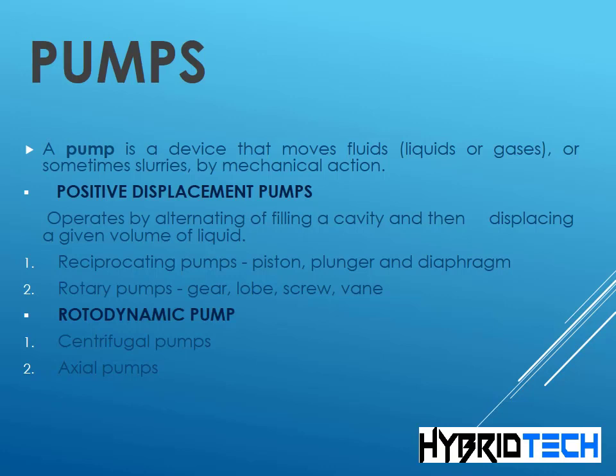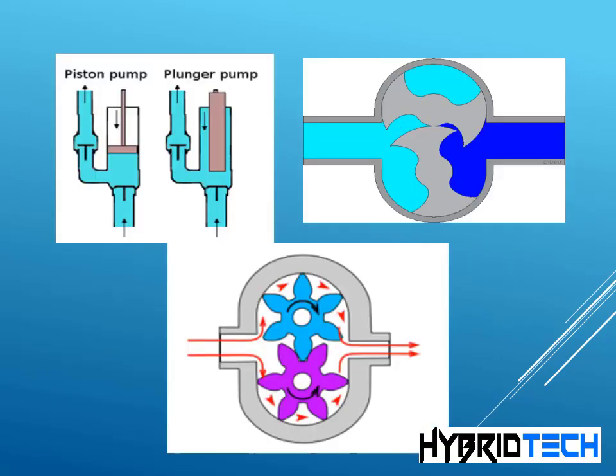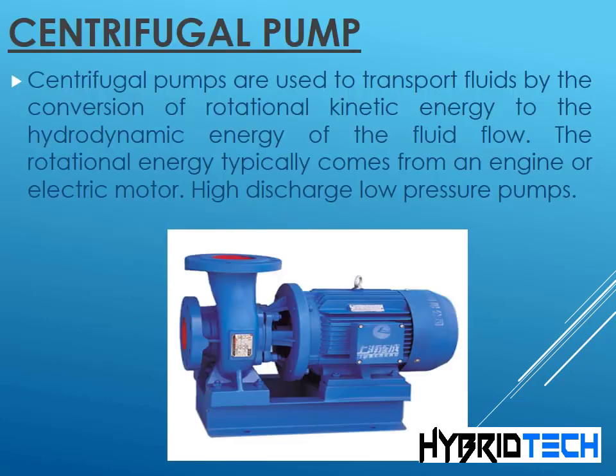Types of pumps include reciprocating pumps (piston, plunger, and diaphragm), rotary pumps (gear, lobe, screw, vane, rotor), and dynamic pumps such as centrifugal pumps. Centrifugal pumps are used to transport fluids by the conversion of rotational kinetic energy to the hydrodynamic energy of the fluid flow. The rotational energy typically comes from an engine or electric motor. These are high discharge, low pressure pumps.